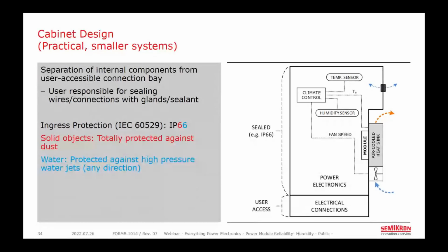Now, again, since these vents here do not keep water vapor out, you still need some mechanism for monitoring the microenvironment inside the cabinet to ensure that the relative humidity is kept low. And for this power range, since most people wouldn't want to pay for a heater or internal fan within here, it's really important then to monitor the operating conditions that we discussed earlier with a low-cost humidity sensor, and perhaps control that fan speed to avoid dropping the heatsink here below that dew point.